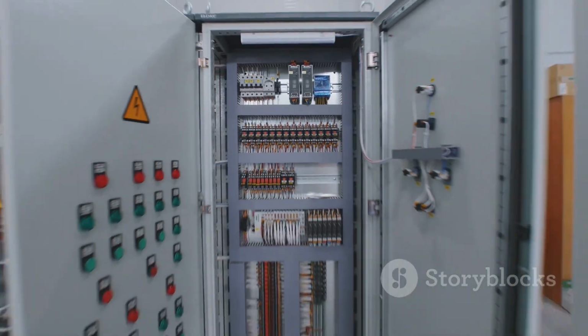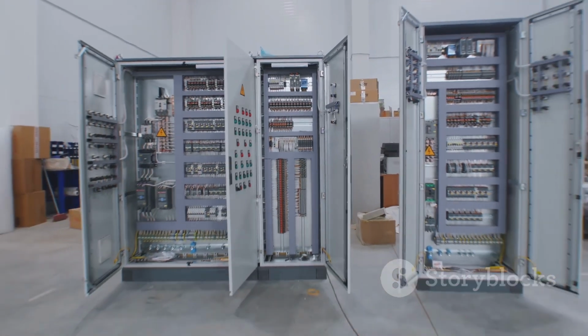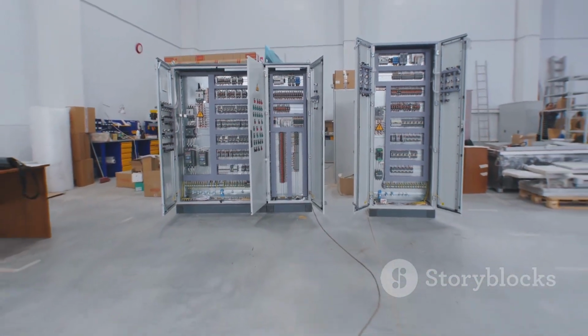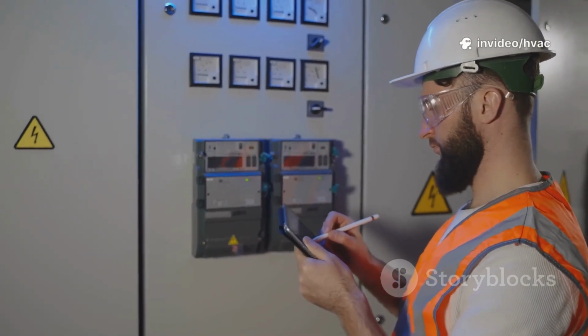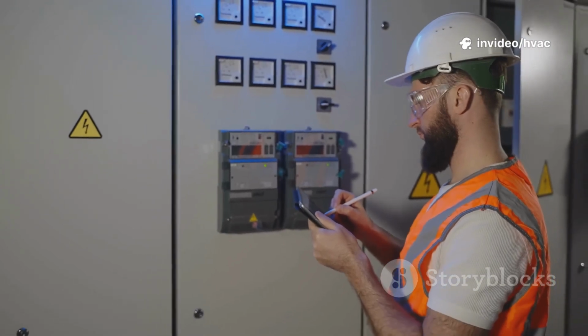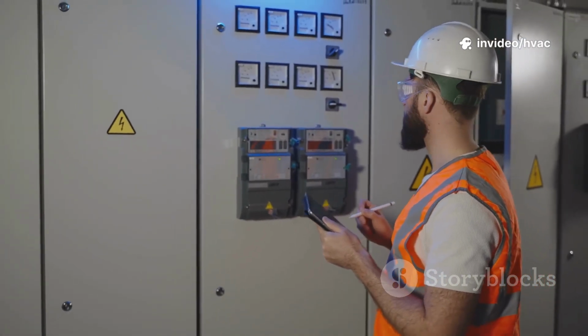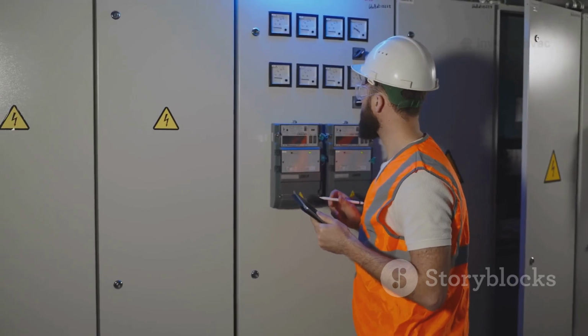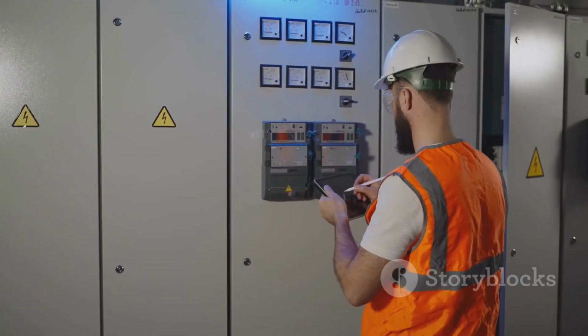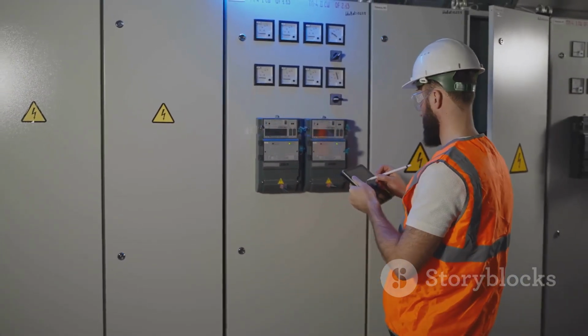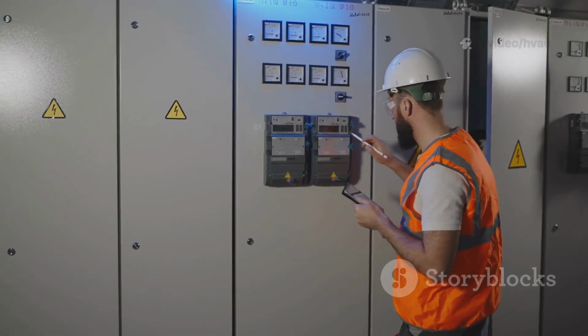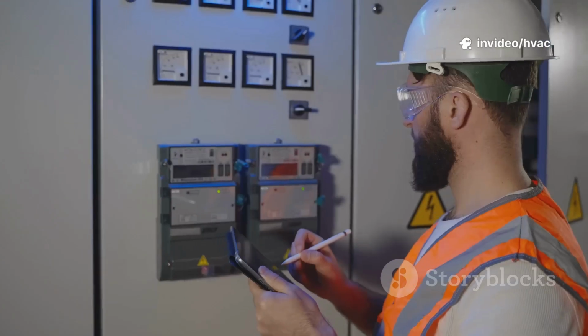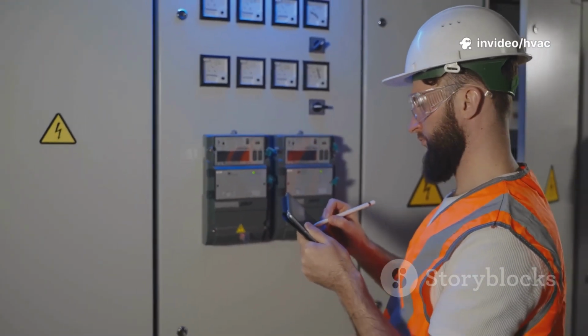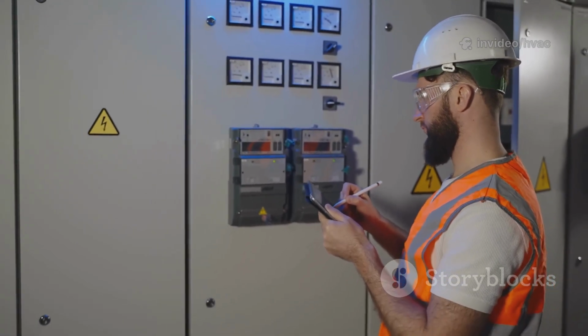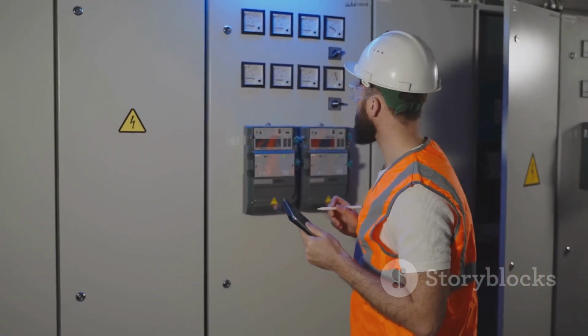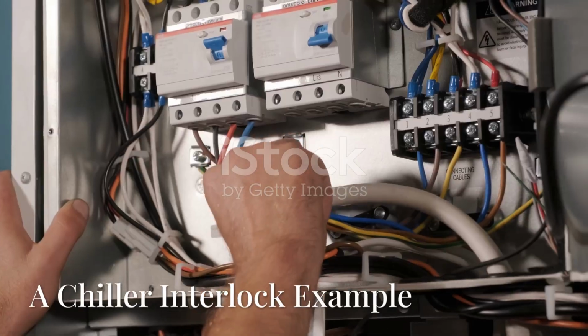Remember, NC contacts are used for safety interlocks, closed during normal operation, opening only on fault or unsafe condition. NO contacts are used for status feedback, open at rest, closing to confirm equipment is running. Always wire these contacts in series for a true permissive circuit. If any NC opens or if an NO fails to close, the system will not run, ensuring maximum safety. Mastering the correct use of NO and NC contacts in these interlocks is essential for safe, reliable HVAC design. Get it right every time.